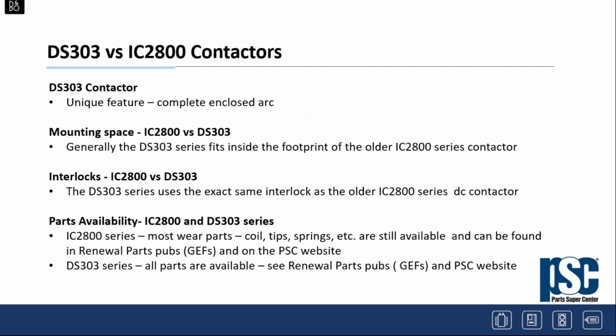Just to give you more information on how these two devices relate to one another: the DS303 contactor, provided today, has a very unique feature in that it has a completely enclosed arc within an arc chute. Unlike the IC2800, the earlier family, and most competitive contactors, where the arc is thrown out into the environment, on the 303 the arc is completely contained within the arc chute.